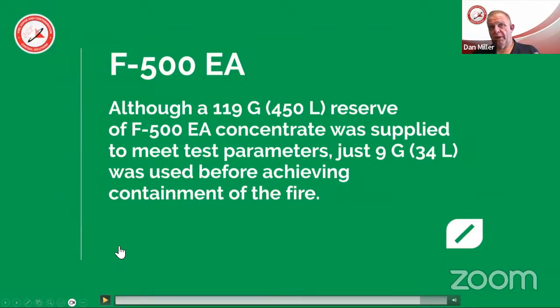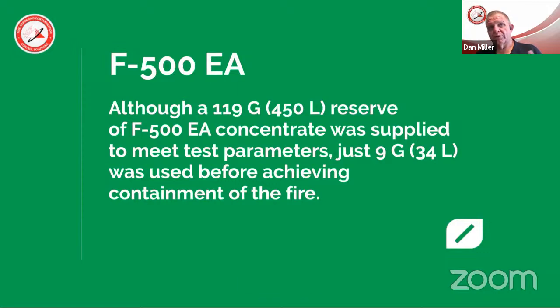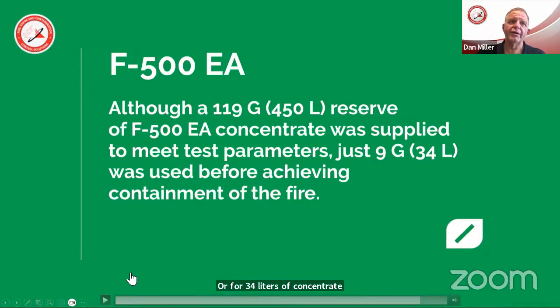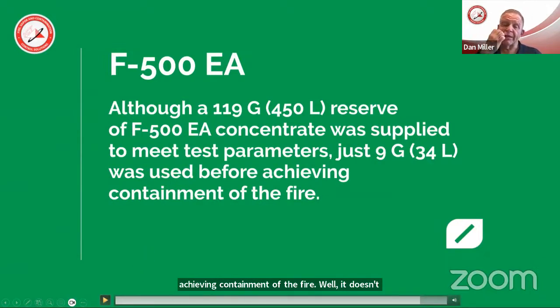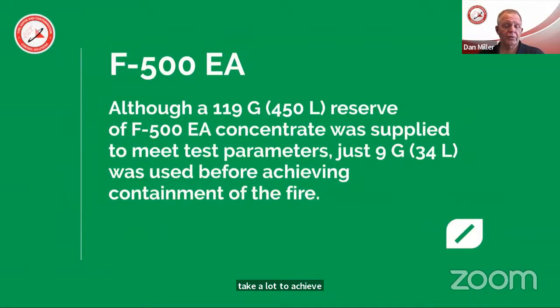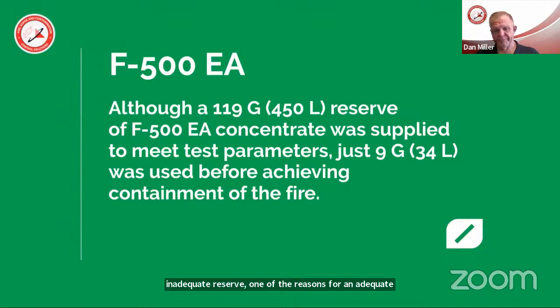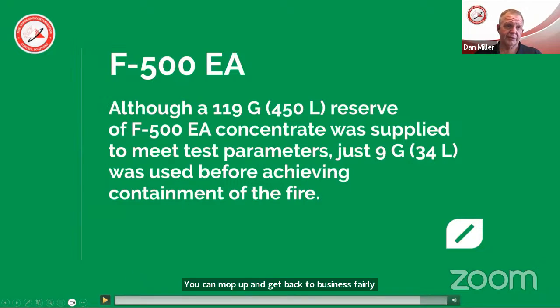Although a 450-liter reserve of F500 concentrate was supplied to meet the test parameters, only 9 gallons, or 34 liters, of concentrate was used before achieving containment of the fire. So it doesn't take a lot to achieve containment of most fires, although you do want an adequate reserve. One reason for that reserve is that in many industrial settings with F500, you can mop up and get back to business fairly quickly because the damage was kept so low.